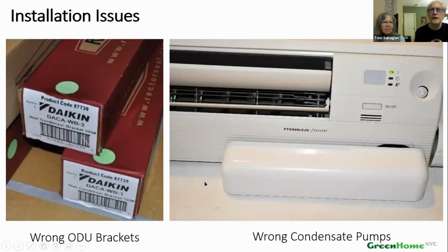Another area that was somewhat problematic was these condensate pumps. Now, in the wintertime, you're not going to have any condensate inside the apartments. But in the summertime, the indoor units serve a function of cooling the air and also dehumidifying. And so that humidity is going to drop down and it's going to have to go somewhere. You can have it drain out by gravity, or in many cases, you don't have much of a choice and you have to pump it out somehow. So we had originally specified pumps that could fit inside the indoor units so that they didn't look like a giant carbuncle on the indoor unit.